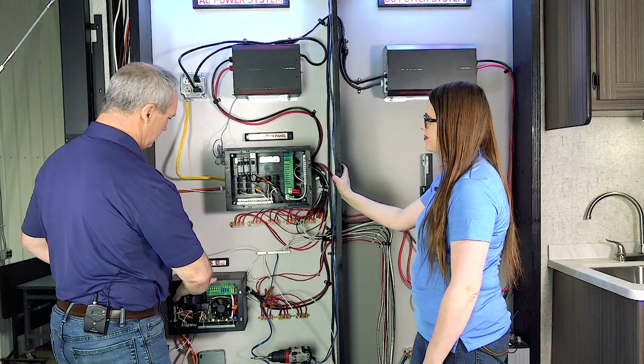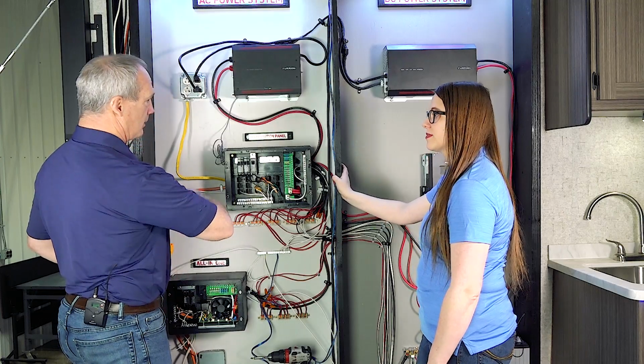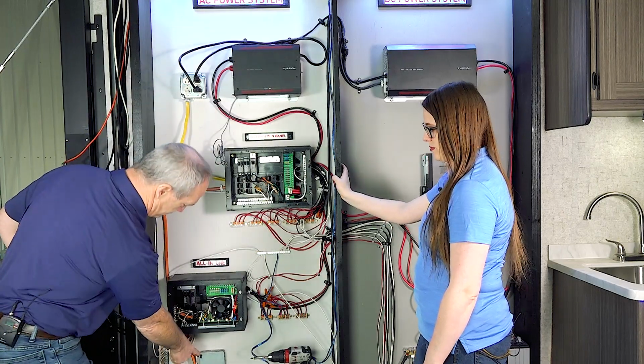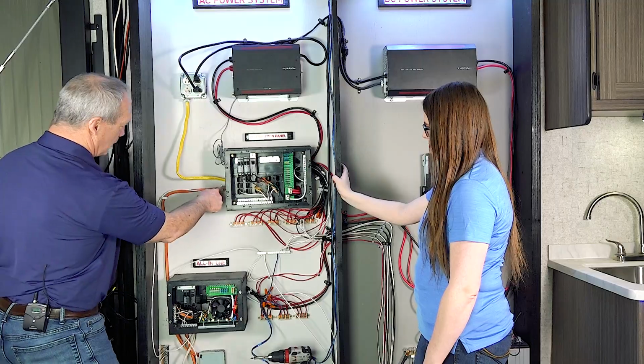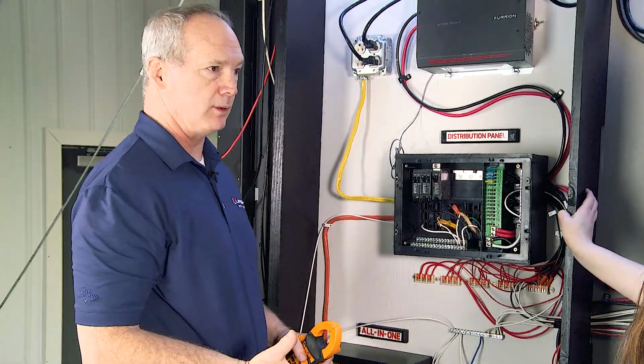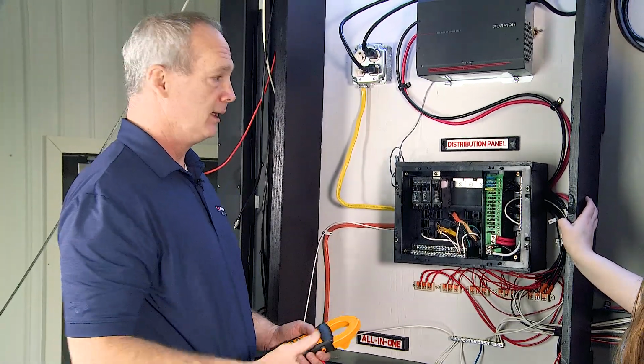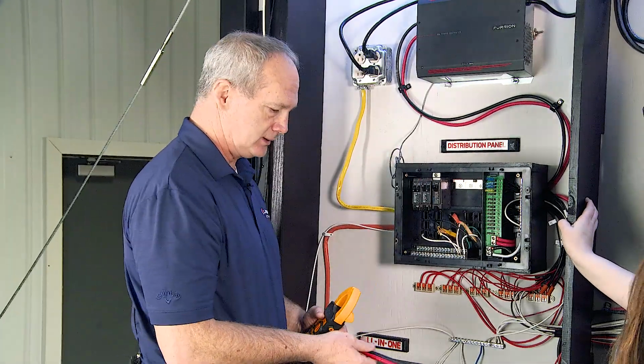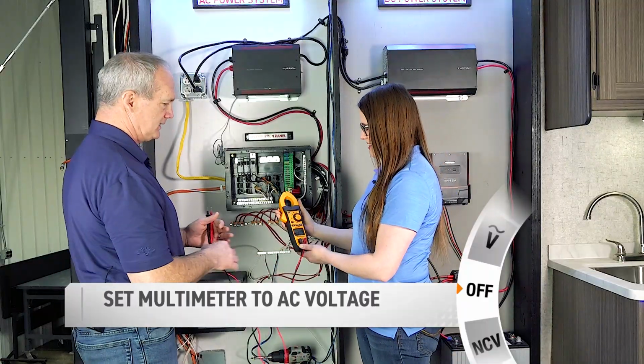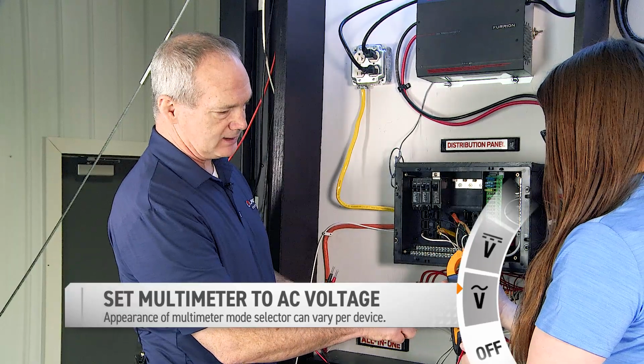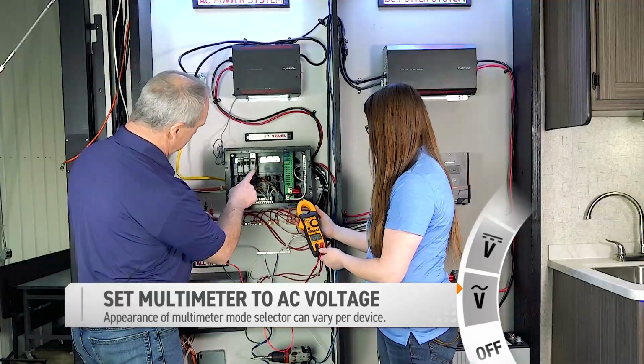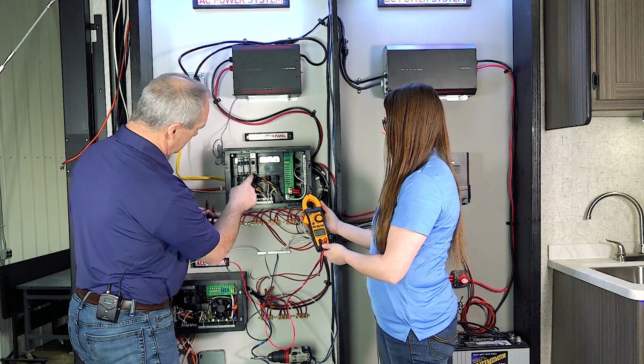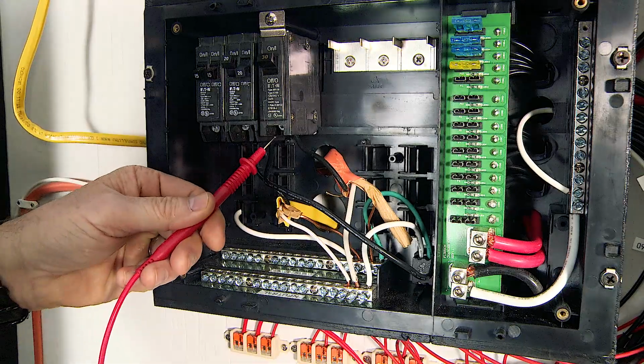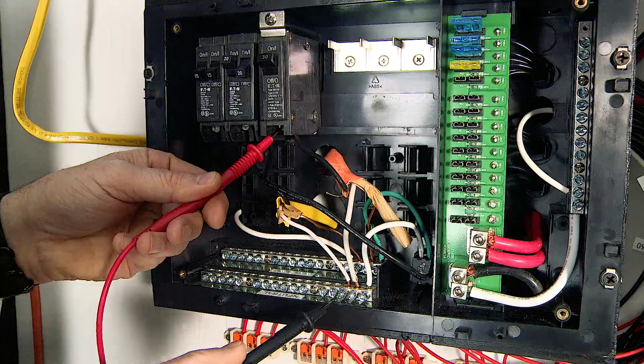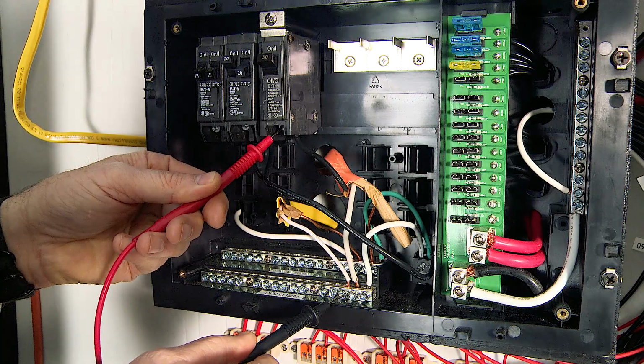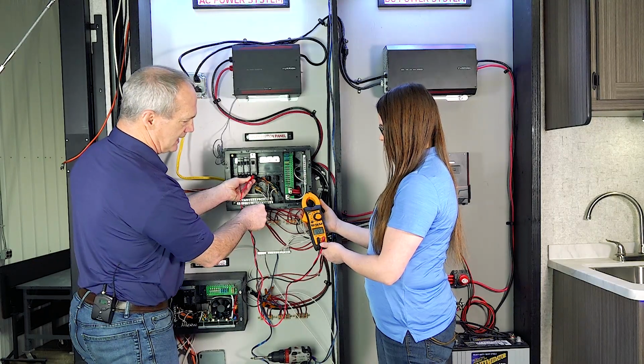Remember, before we were checking the power coming in from shore power. Follow that orange wire up, that's your 120 volts AC, and we need to make sure that power is there. Can you hold that for me? Absolutely. Make sure your meter is set to AC voltage; we're testing this main breaker with 120 volts AC. We'll take the power lead to the power wire and put it on ground, and we should have 120 volts AC, and we do.